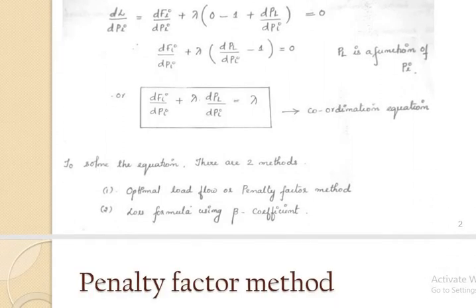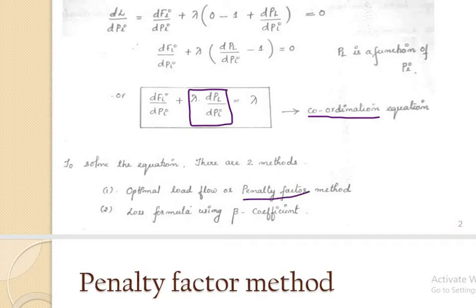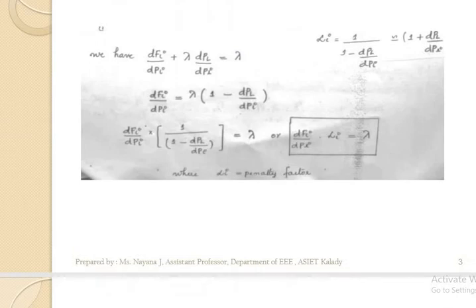Refreshing, this was our coordination equation: dFi/dPi + λ × dPL/dPi = λ. This dPL/dPi is the term associated with transmission loss. To solve this term, we have two methods. One is the penalty factor method and the other is the beta coefficient method. In the penalty factor method, the penalty factor is represented as 1 / (1 − dPL/dPi).